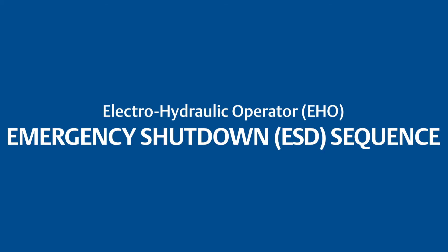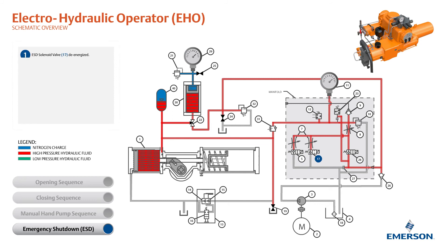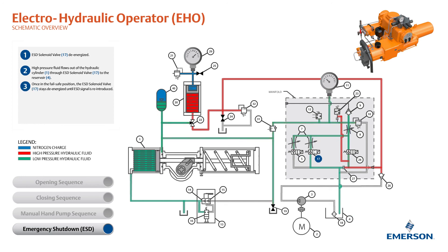This is the theory of operation for the emergency shutdown sequence of the Bettis EHO. The emergency shutdown sequence is triggered by the loss of an ESD signal and/or main power supply. The ESD solenoid valve is de-energized. The high-pressure fluid flows out of the hydraulic piston through the ESD solenoid valve to the reservoir. Once in the fail-safe position, the ESD solenoid valve stays de-energized until the ESD signal is re-introduced.